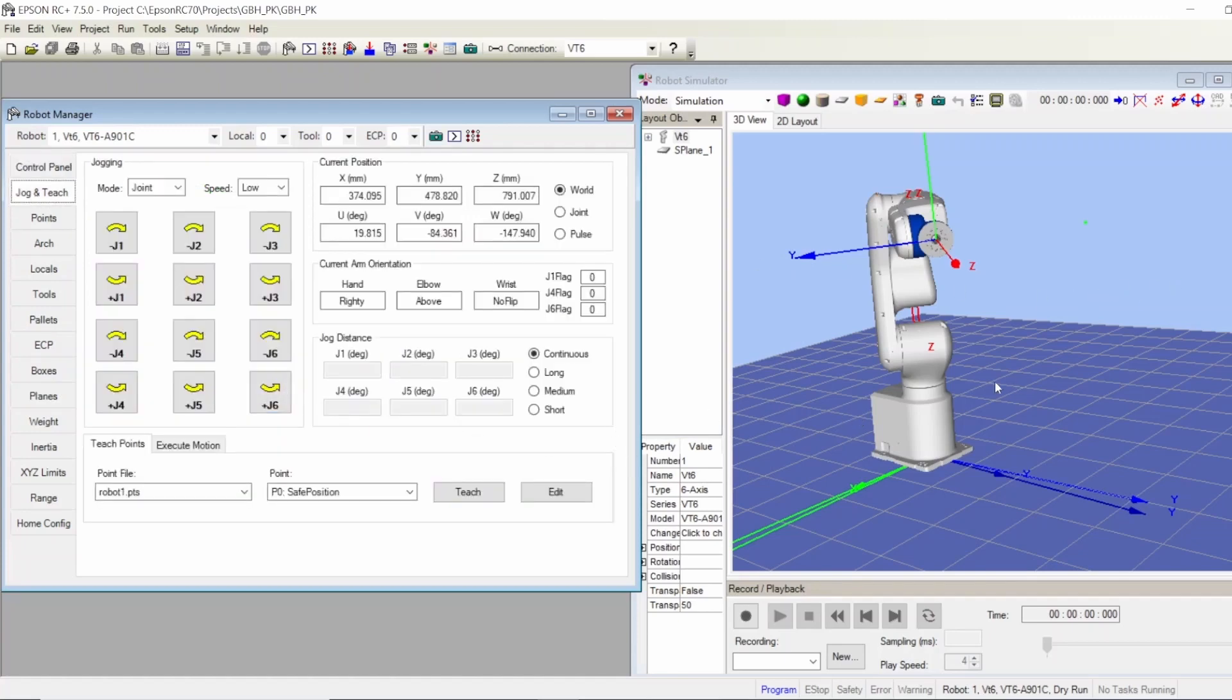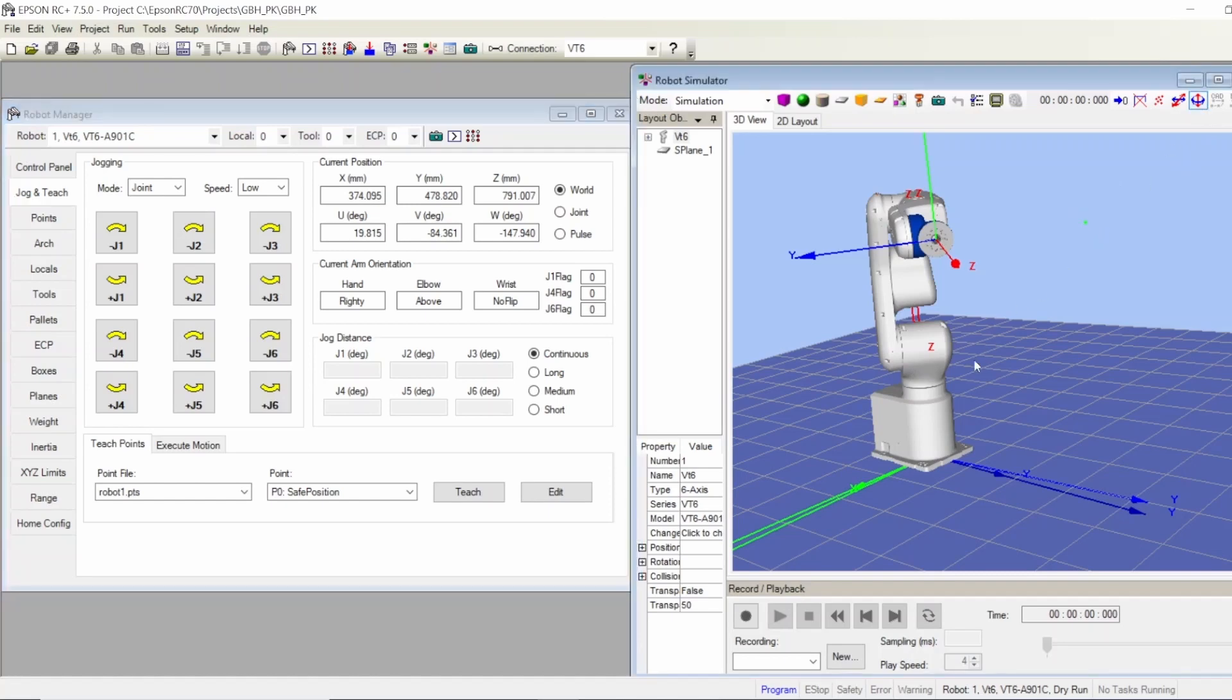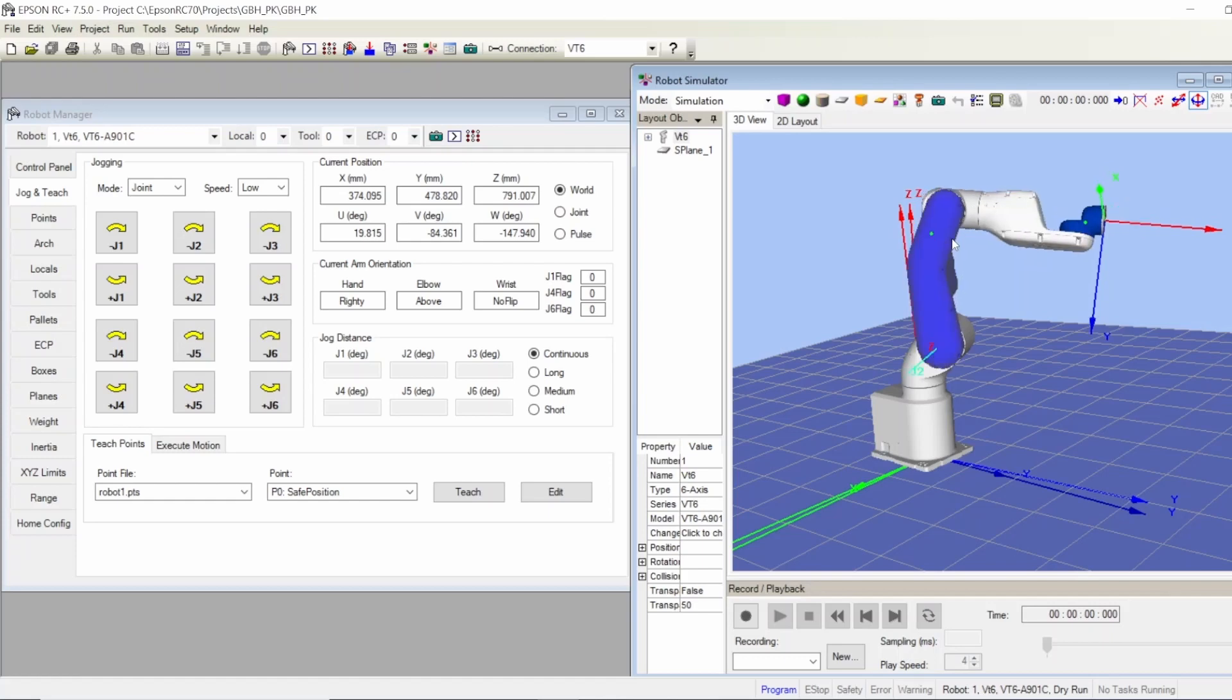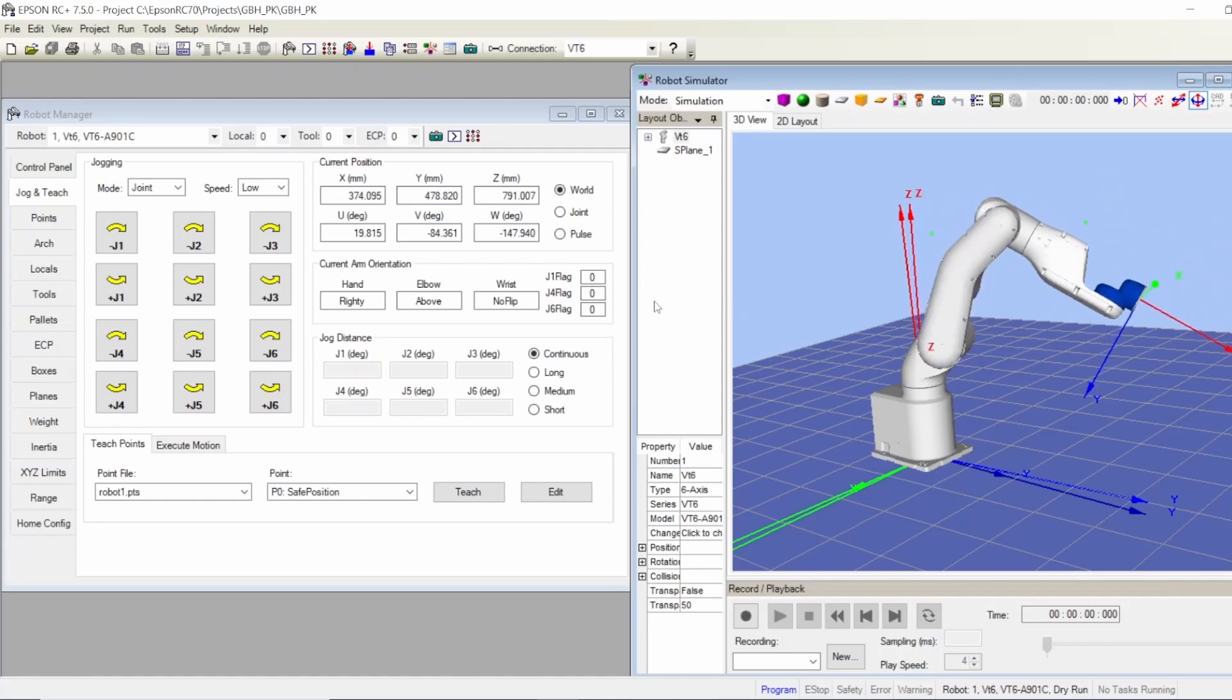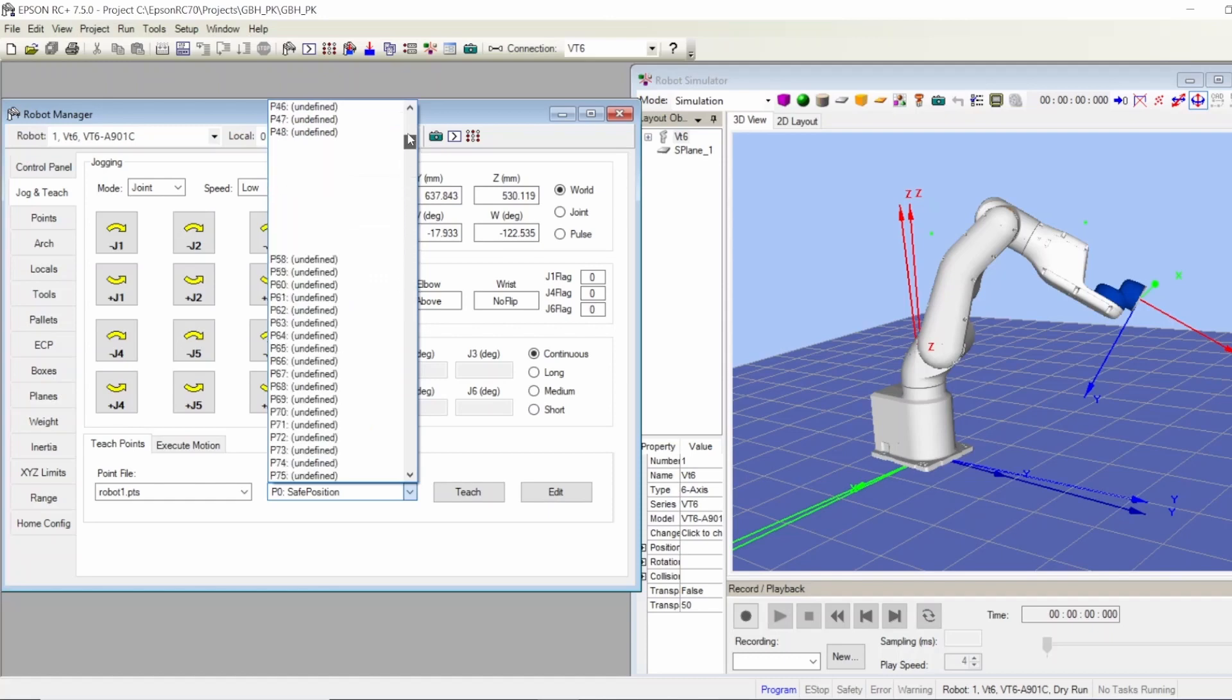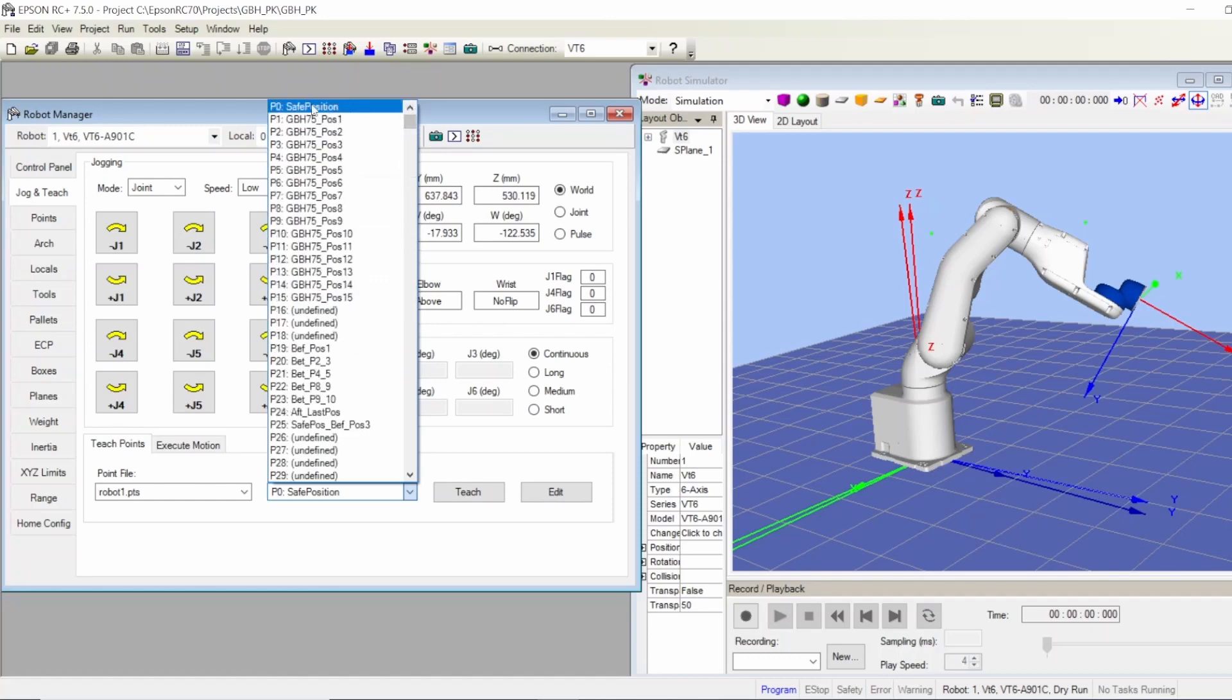Now if I want to teach another position - this is my home, now I want it to go a little bit to this side. I want this one to turn this way, this one to go down. I want this to be the safe position, for example, or any position. I come to the jog and teach, and after I make sure of this position, I go to teach point. I choose any point I want. I have some points to re-teach, but I can choose a new point or an existing point, edit it and press teach. So now this is my safe position.